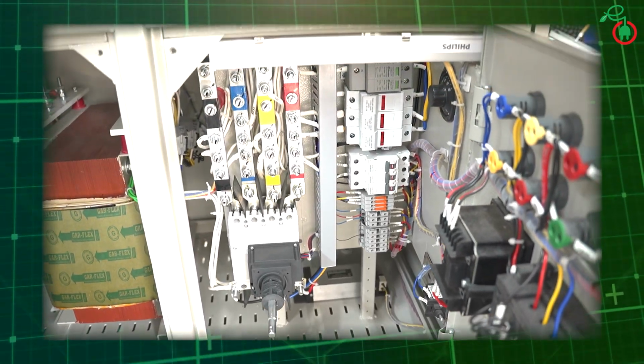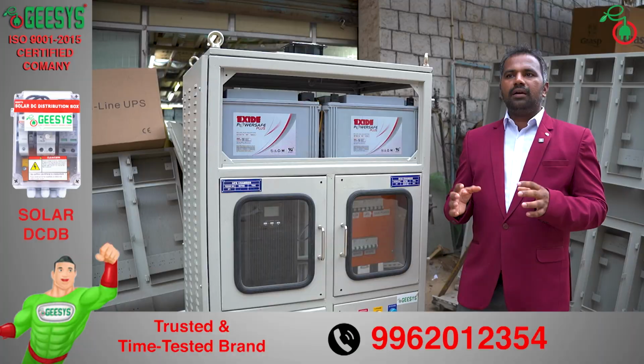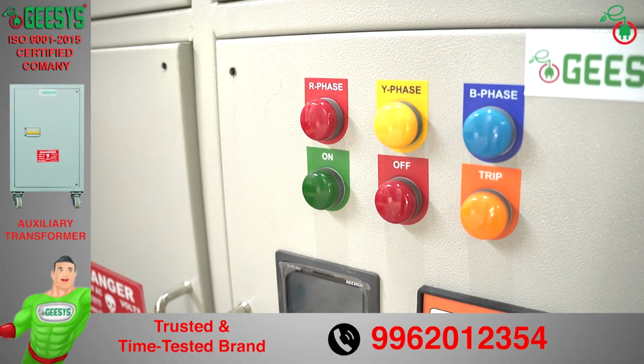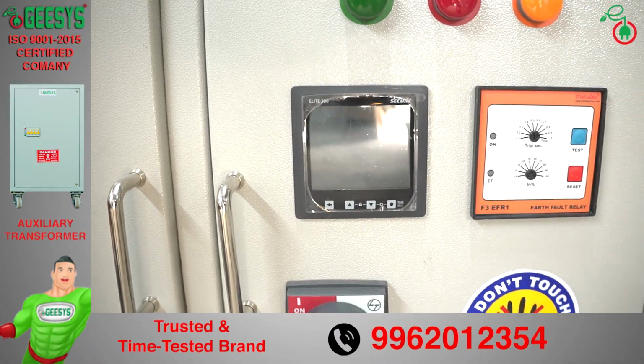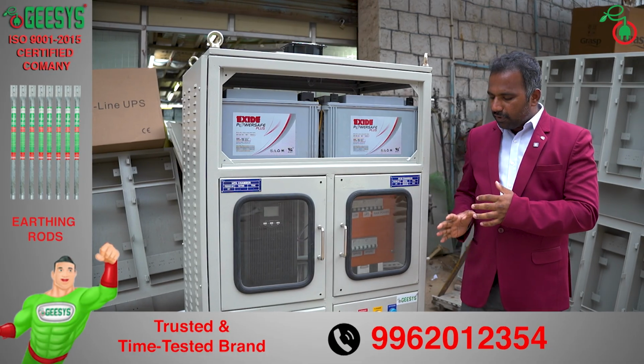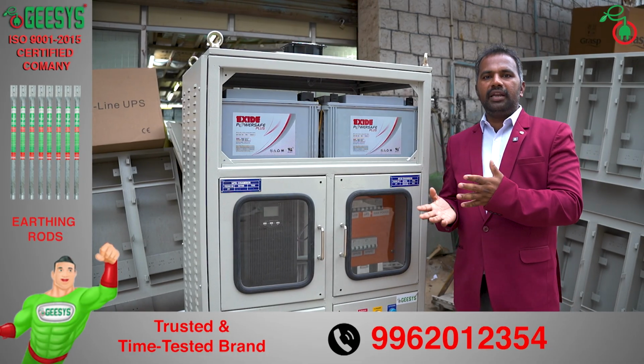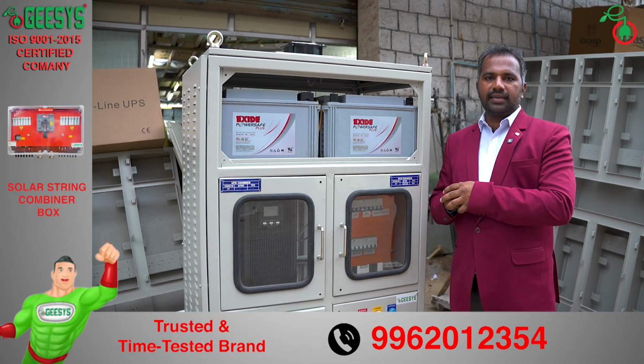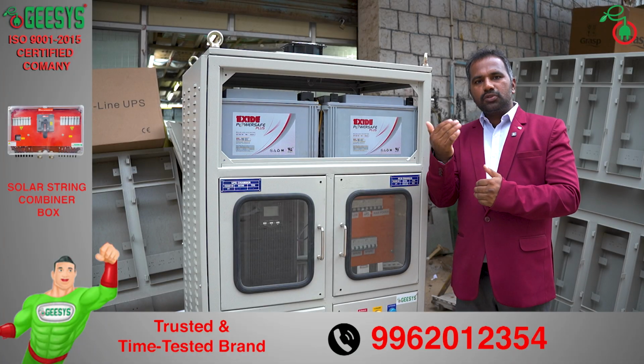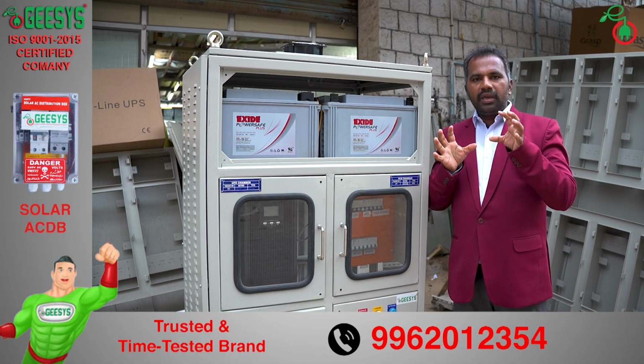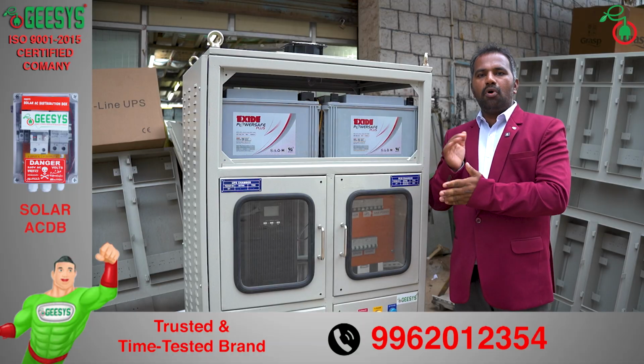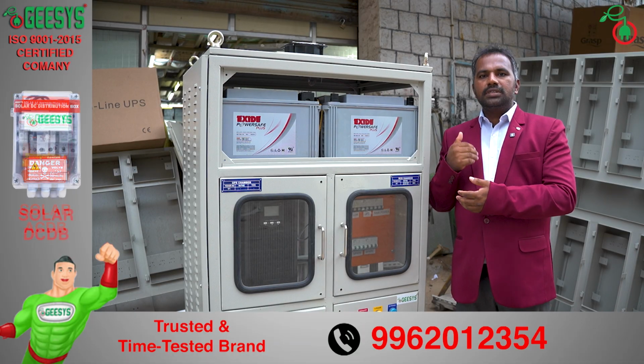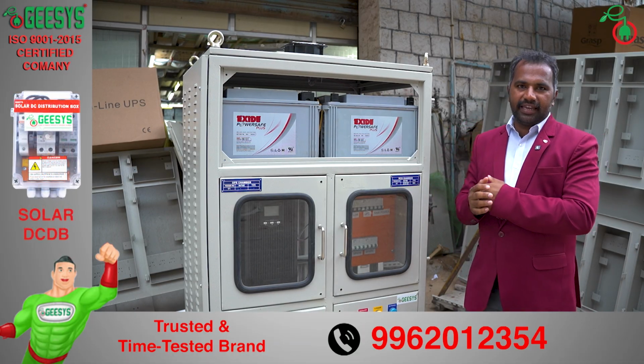The power distribution board consists of major safety and protection equipment, such as the RCCB monitoring with voltage display, and also the function of checking the on-off trip indication of the breaker output of the auxiliary transformer. I am saying the entire power which goes out from the auxiliary transformer is monitored and protected with overload, short circuit, over voltage, surge protection, and also earth leakage protection.